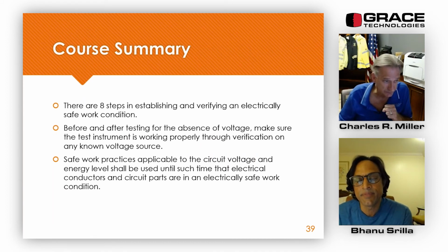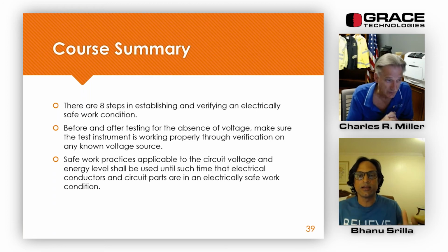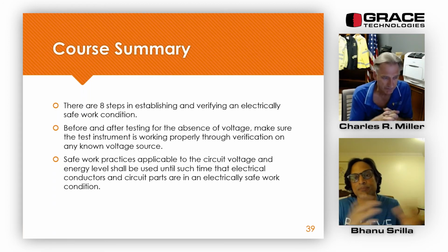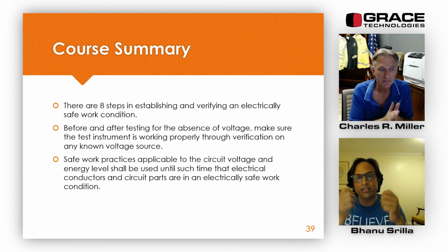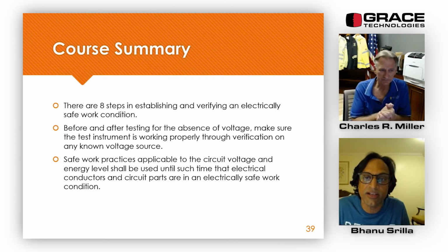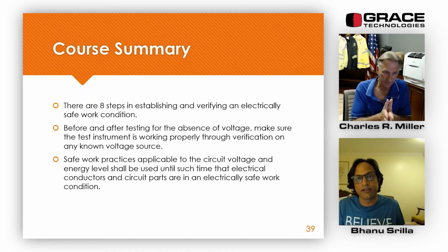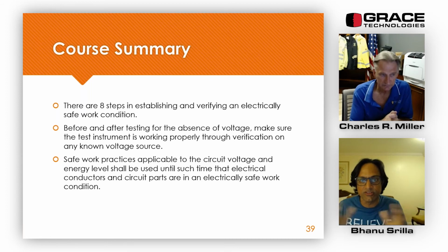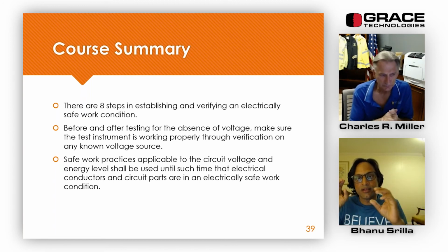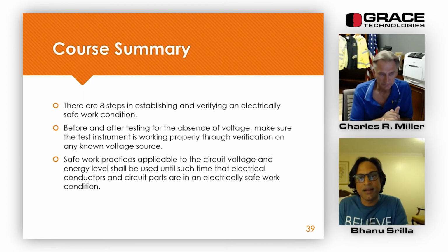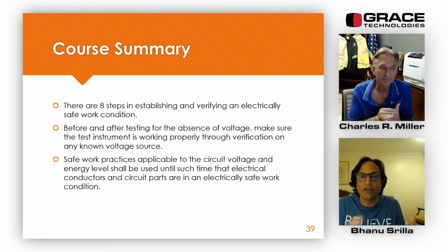Actually, the intent of the person who put in the public input was primarily to ensure that door-mounted devices cannot be used for absence of voltage testing. But when you put in each point of work, what it means is, even if you verify the absence of voltage from outside the door with our device or a device using an exception, whichever it is, it's only verifying the absence of voltage at that given point. When you open the cabinet, it's only verifying to where it's connected. Other than that, you still need to verify the absence of voltage at each point of work if you go by the same definition.